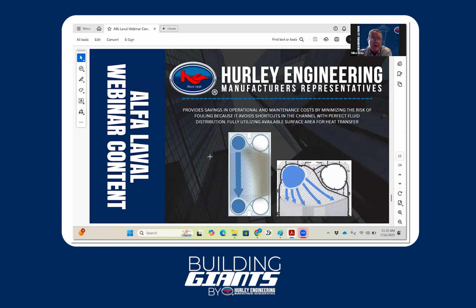Here it goes over what we talked about before, where you get fouling. We want to utilize as much of that plate as we can. You can see if we have a round port and you don't have that curved flow as it goes into the plate itself, you can have some dead areas, and that creates areas of fouling or buildup, whether it's biological or mineral or whatever the case may be inside the exchanger. And on the right, you can see utilizing curved flow, we're guaranteeing that we're spreading that flow out before it goes down the plate so that we get more even flow and have no dead areas within the plate itself. Leads to less maintenance down the road and better heat transfer.